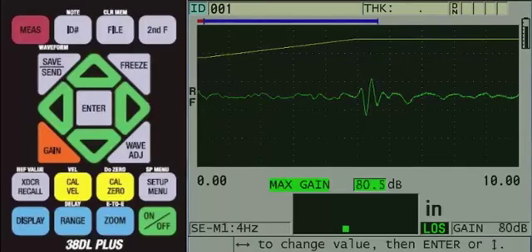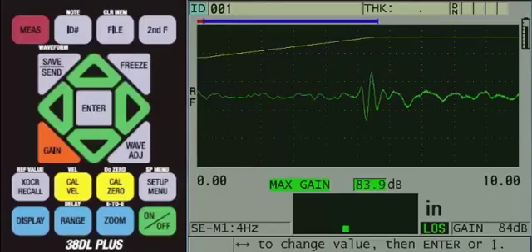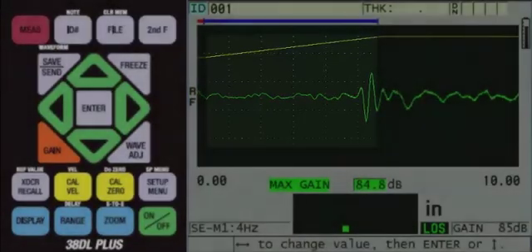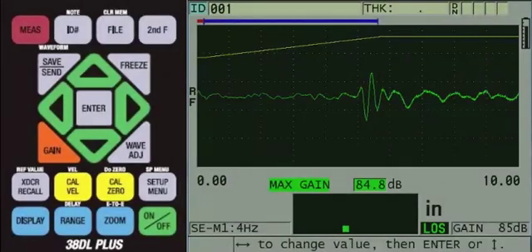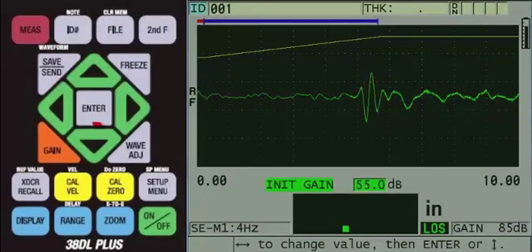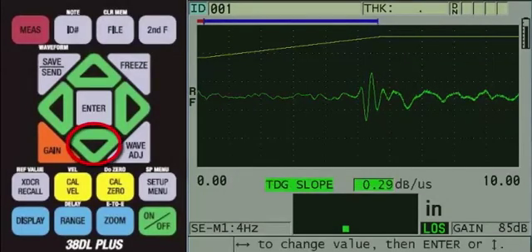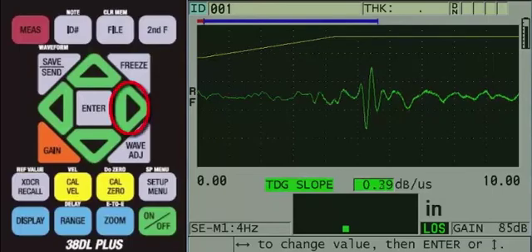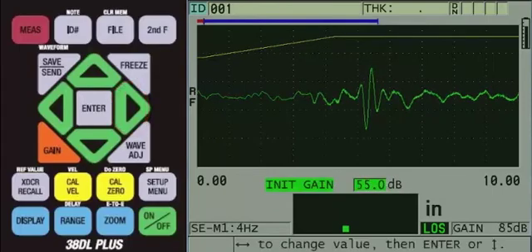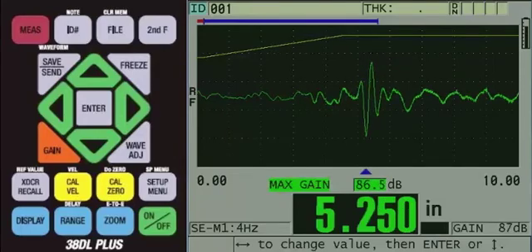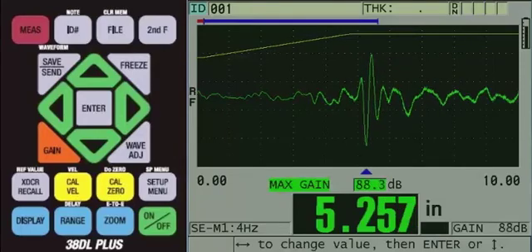Eventually, the back wall echo is no longer under the MAX GAIN line and is now under the TDG slope line. Therefore we need to increase the TDG slope. To do this, press the down arrow to TDG slope, then press the right arrow to increase the TDG slope. You may need to go back and forth and adjust both the TDG slope and the MAX GAIN until the back wall echo is detected.